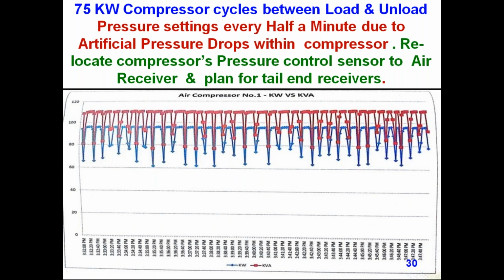This is what system integrators also do when they install a retrofit VFD to the compressor. They always try to locate the pressure control sensor on the receiver only, not on the compressor, because it gives a non-pulsating signal to the monitoring and control.